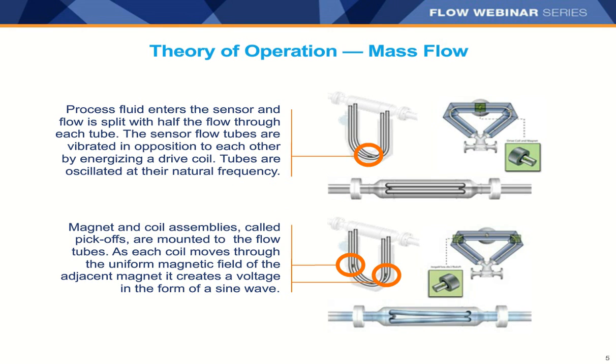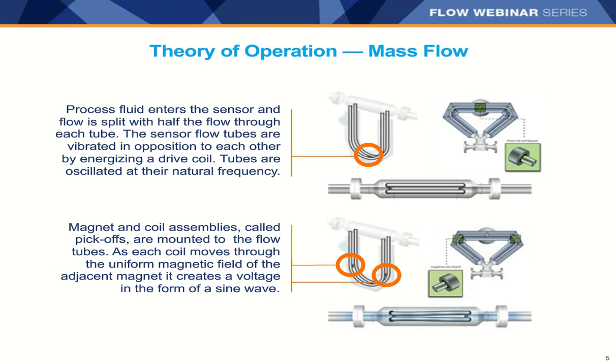The theory of operation for mass flow is quite simple. The process fluid enters the sensor and the flow is split halfway through the sensor tube. The sensor flow tubes are vibrated in opposition of each other by an energizing drive coil at their natural frequency — think of this like a tuning fork. With the Coriolis meter, we send a pinging signal from our transmitter to the drive coil, constantly vibrating these tubes at their natural frequency so the vibration does not die out.